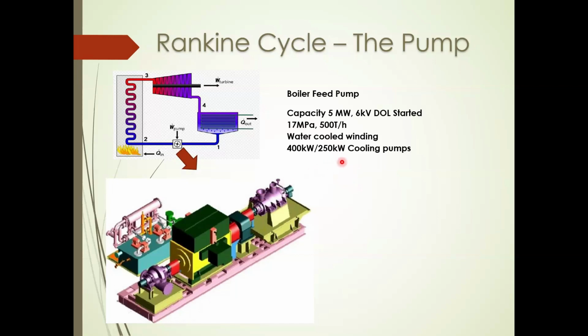circulate lubrication oil throughout the operation of this boiler feed pump, and it draws a very large current, of course. Because of this current, the winding gets heated up very fast, so you have to cool the windings as well. To cater to all the cooling requirements throughout the power plant, we have a separate auxiliary system, circulating cooling water: the cycle cooling water pump, which has a 400 kilowatt rating, and another cycle pump with a 250 kilowatt rating. So all these apparatus have to work prior to starting this boiler feed pump. These are essential auxiliaries which are also powered by the 6 kV station supply. All these things have to be there in order to run this pump.